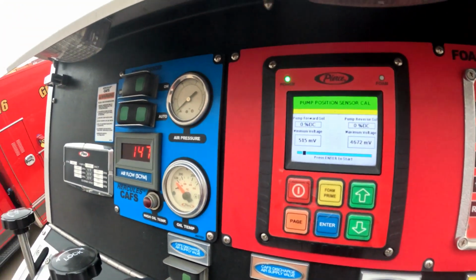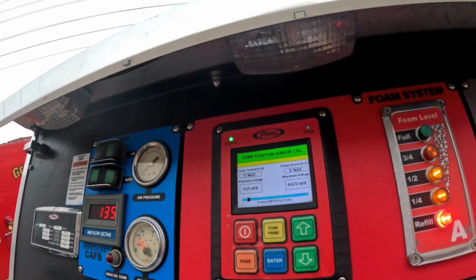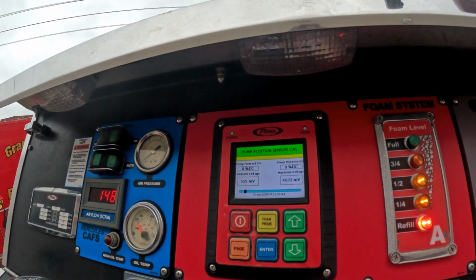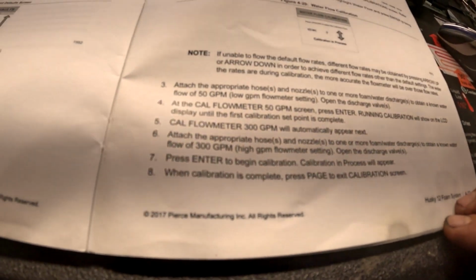So at this point, I'm just going to calibrate my water flow meter, and I'll show you guys how to do that. And then we will prime the pump and try to flow foam and see what we get. Since those voltage readings are in acceptable range, I'm not going to try to do the recalibration. I'm going to see what we get after we recalibrate the water flow meter. Okay, so we're going to be calibrating the flow meter, the water flow meter. So what we're going to be doing is we're going to be doing it at 50 gallons per minute and 300 gallons per minute. All right.